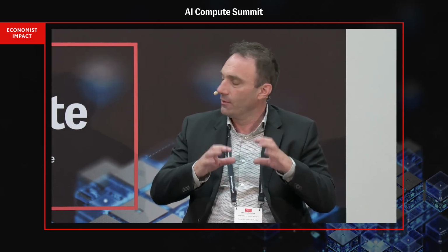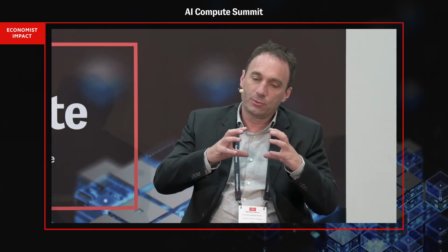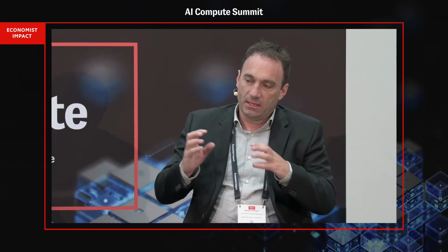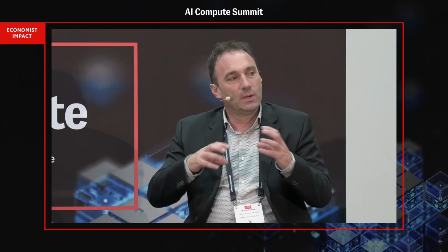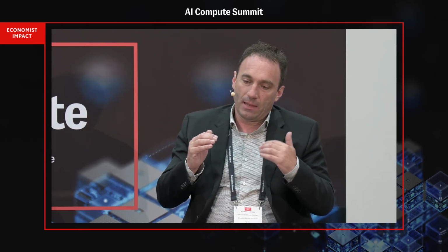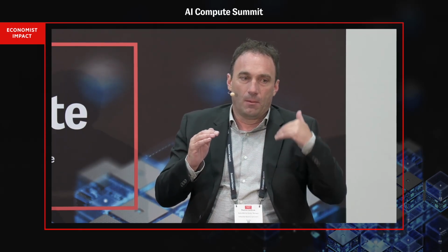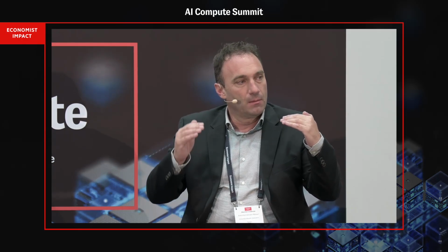And as I said at the beginning, Edge AI is mainly about inference. In this case, we don't train a model in a room controller. No, that won't be possible, but we can fine-tune some parameters. So we have this model, which every day is taking control over the room and learning, fine-tuning some of these parameters week after week, so that we are able to reach a better target in terms of comfort, while reducing the energy consumption by 5 to 15% in some cases.